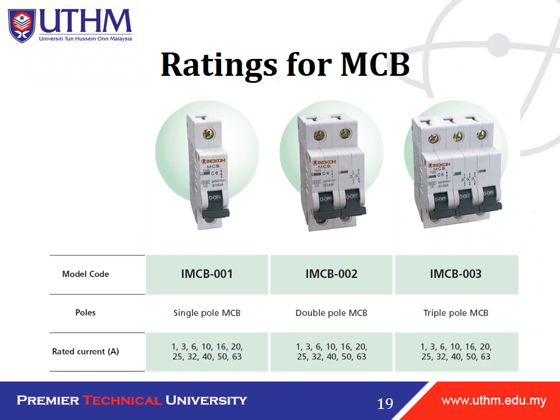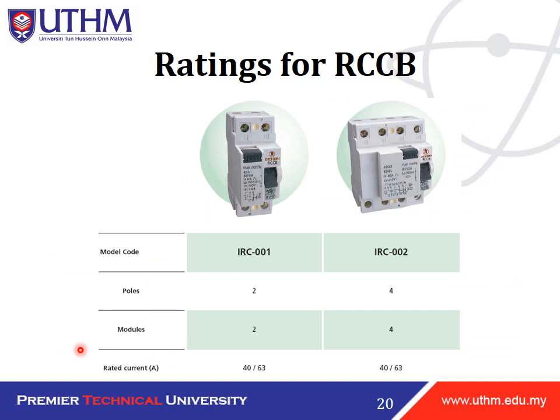Okay. This is the rating for MCB, which you can read by yourself. So this is the example for single pole MCB. This is the double pole MCB, and then we have triple pole MCB. This is SP, single pole, double pole DP, and triple is TP, with their respective rated current. And then this is the rating for RCCB. So we can see that this is for two poles, I have two here, and then this is for four poles. Alright.